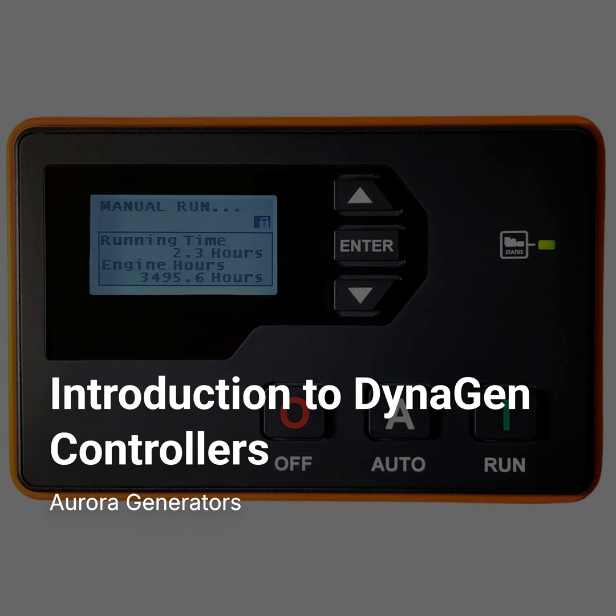Yep, they have several types of timers. Engine logic timers manage the start-stop sequence steps. Like what? Things like a delay to start after the signal, preheat time for diesels, crank time duration, crank rest time between attempts, energize-to-stop time for certain engines, and that cooldown timer we talked about. Fine control over the sequence.